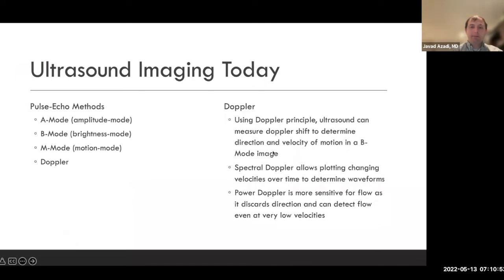And then finally, Doppler. Doppler requires the Doppler principle, and ultrasound can measure the Doppler shift to determine the direction of velocity of motion in a B-mode image. So Doppler can be superimposed on a B-mode image. Doppler can be attained without the B-mode, but it's a little less useful if you don't know what you're measuring. Spectral Doppler allows us to plot changing velocities over time to determine waveforms. So this is very helpful if you see something vascular and you want to know if it's arterial, venous, or just kind of noise from something flowing, because not all Doppler signal is blood flow.